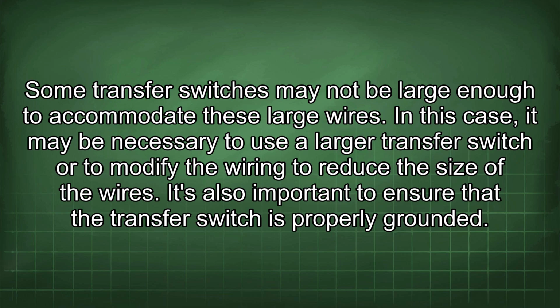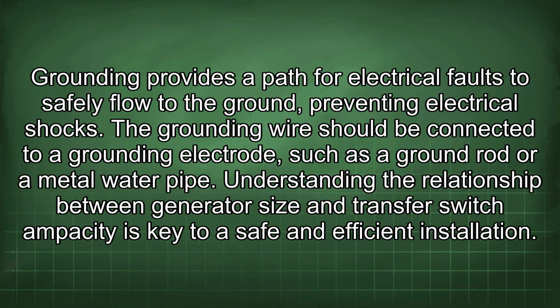It's also important to ensure that the transfer switch is properly grounded. Grounding provides a path for electrical faults to safely flow to the ground, preventing electrical shocks. The grounding wire should be connected to a grounding electrode, such as a ground rod or a metal water pipe.